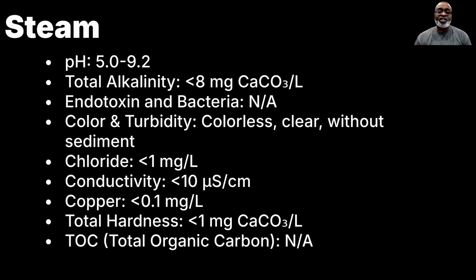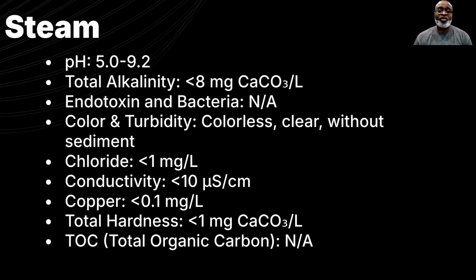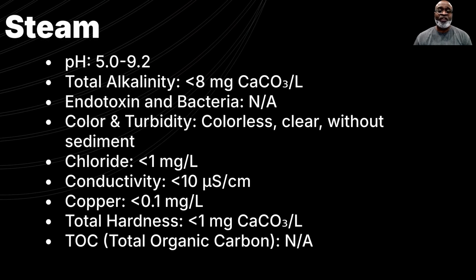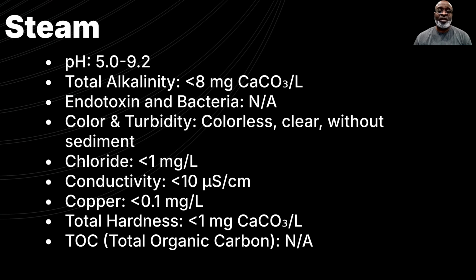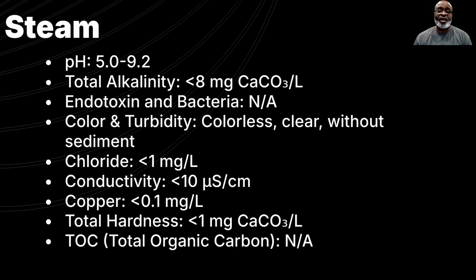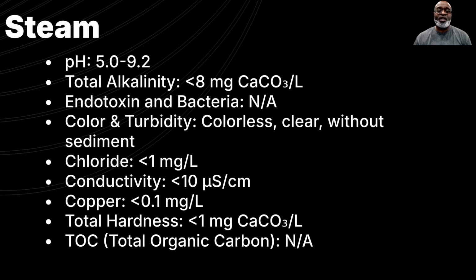Steam is the final sterilization method used in medical device processing and steam sterilizers. It plays a critical role in ensuring that devices are free from contaminants and safe for use. To achieve effective sterilization and comply with ST108, steam must meet strict quality parameters. The following limits apply to steam: pH 5.0 to 9.2, total alkalinity less than 8 milligrams per liter of calcium carbonate to minimize residue buildup.